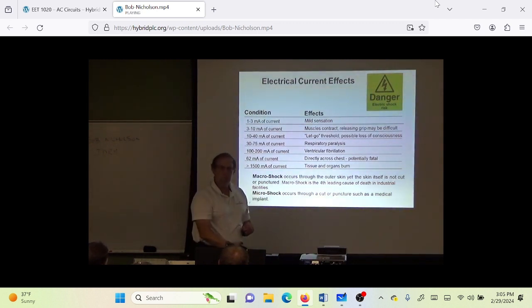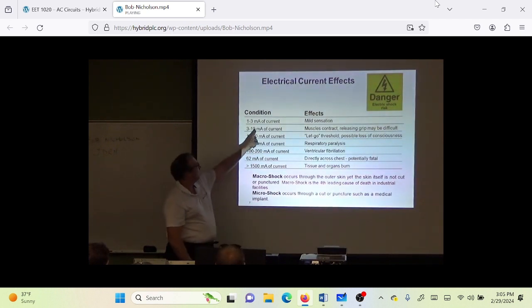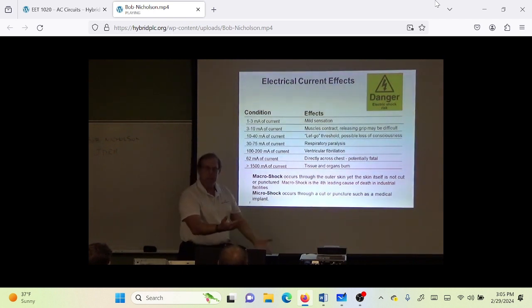When you add up the resistance between my finger and that ground rod that's somewhere in the site, you add up all that resistance, that's current. So what happens is, not much current is going to flow through my body. So when you felt a poke, you felt 1 to 10 one-thousandths of an amp actually passing through your body. All of the rest of it was taken up by the resistance. Now, if I would have touched this and I would be standing outside, I'd be dead. Because I would not have the carpet, the mat, the concrete. The closer I get to that ground rod, the worse this is going to get.